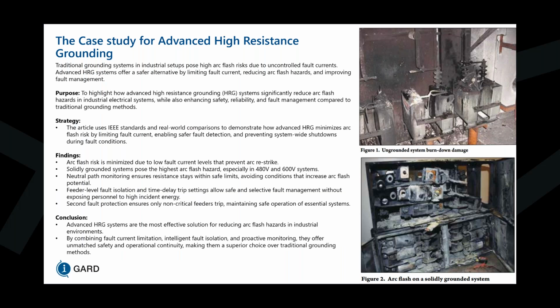Now, if you didn't have the DSP system in place, your LSI breaker will pick up through the instantaneous function and trip at 6 to 8 times its current level. But it still takes time to get to that 6 to 8 times current level, so our selective tripping method is slightly faster than that instantaneous function.